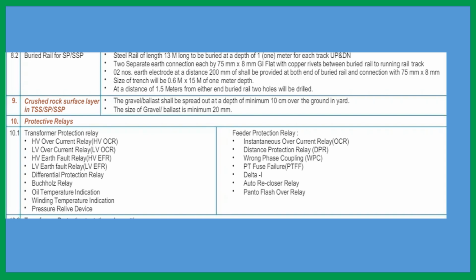Buchholz relay is used. Oil temperature indication, already we have seen its setting, how much? Alarm is at 75 and trip is at 85, and for winding it is 95 and 85. Pressure relief device, PRD. PRD is used when gas is formed, any internal short circuit and everything. The tendency is to burst the transformer tank due to huge gas formation. Then the pressure relief device releases the pressure, and will trip both the circuit breakers of the transformer.